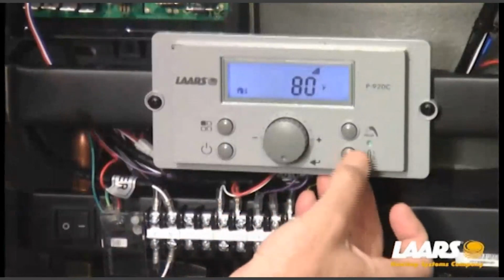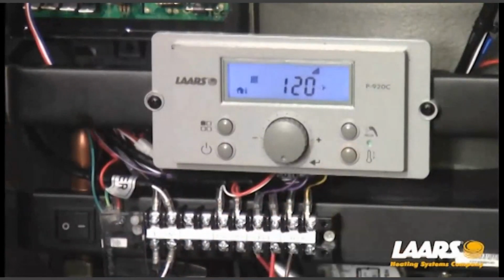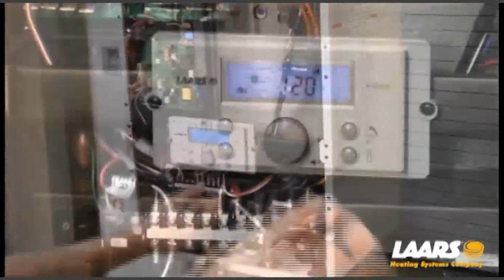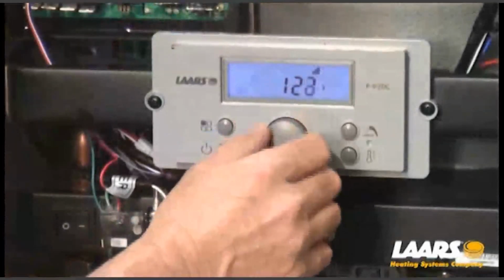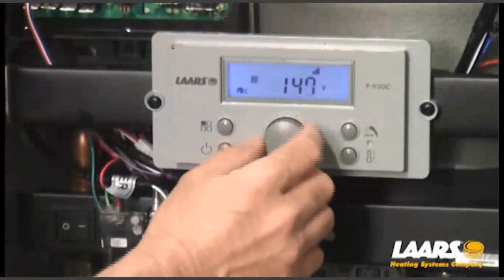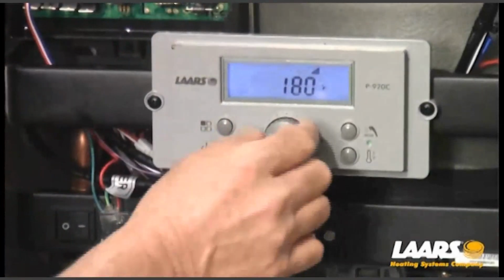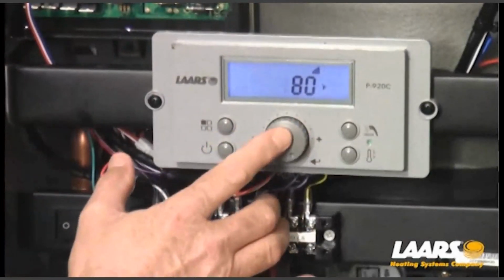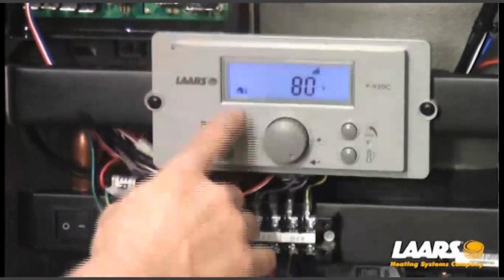The thermometer symbol, right here, the lower right button, press that once, and it'll show our defaulted setting of 120 degrees for central heat. You can adjust this to your system, so if you have in-floor radiant, maybe you only want 120 or 130. Hydro air, you may want 160, or baseboard heat on the coldest day of the year, you may want 180. So for this example, I'll set it up for 180 degrees by adjusting the dial. Once I get to 180, press the select button once, it stored it, and now I'm back to my home screen.